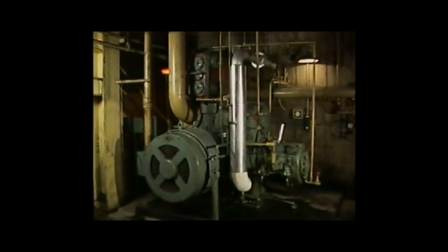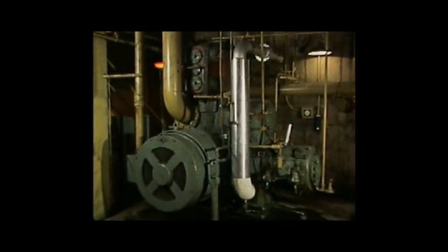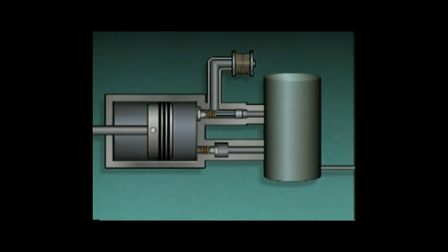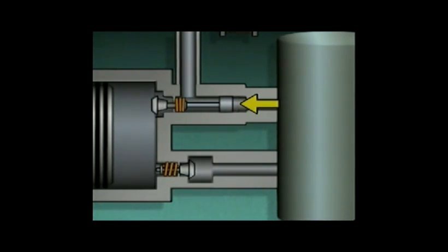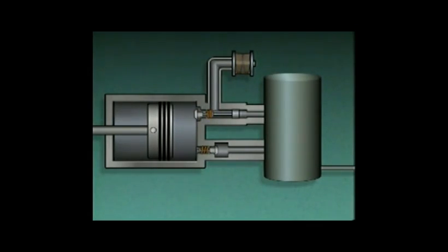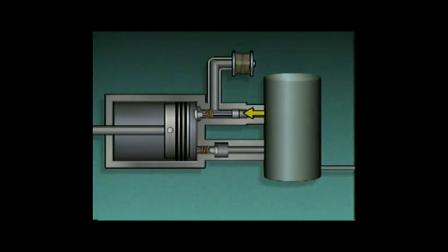Large compressors tend to be more efficient if they operate continually, so one device commonly used to prevent over-pressurizing the receiver is an inlet valve unloader. The unloader consists of a piston and a connecting rod connected to the inlet valve on the compressor, with a pressure sensing line connected from the unloader to the receiver. Gas from the receiver fills the pressure sensing line, and as receiver pressure increases, it moves the piston and connecting rod and opens the compressor's inlet valve. With the inlet valve open, gas entering the compressor is pushed back out and is not compressed. When pressure in the receiver decreases, the pressure on the unloader piston also decreases, allowing the inlet valve to move normally and the compressor to resume normal operation.